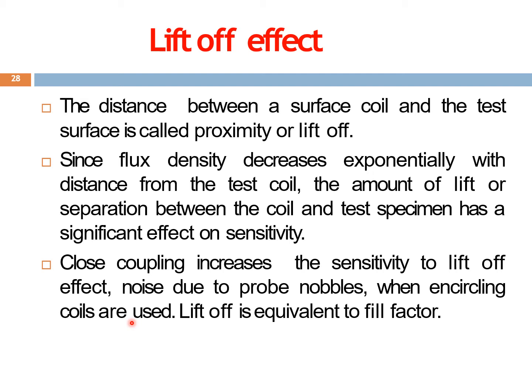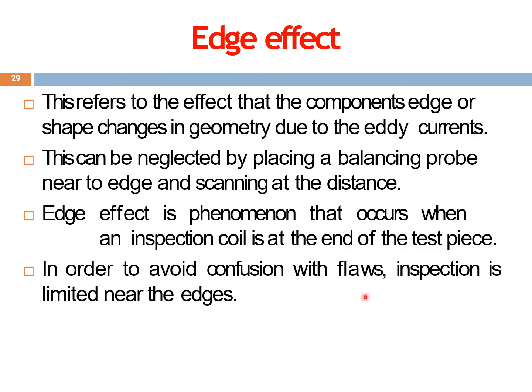The noise is actually the variation in the signals, right? So the lift off is equivalent to something called fill factor. That fill factor we'll be discussing. So the lift off effect is an important factor that controls the accuracy of the testing method. Now, edge effect, right?